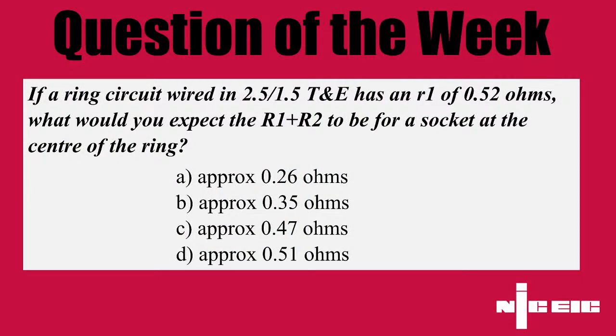Okay, so without any further ado, I'll just remind people of what our question of the week was. A little bit of maths, but I think a very useful question for those that perhaps were a little bit unaware. If a ring circuit wired in 2.5/1.5 mil twin and earth had a little R1 of 0.52, what would you expect the R1 plus R2 to be for a socket at the centre of the ring? So we've got a ring circuit wired in 2.5/1.5 mil, pretty common for a domestic scenario. The R1, which would be the end to end of your line conductor, measured 0.52, and then while you were doing the continuity of circuit conductor tests, what would you expect your R1 plus R2 to be at a socket which was at the centre of that ring?